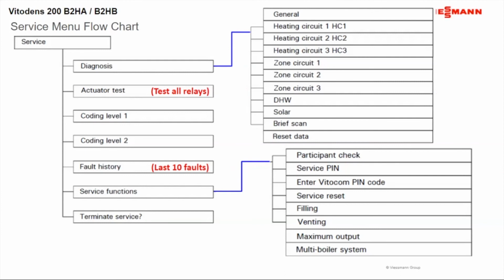The neat thing with the fault history is that it gives you the last top 10 faults. Number 1 is your newest fault, number 10 is your oldest. If a new fault comes in, number 10 drops out, and number 1 gets replaced with the newest fault.